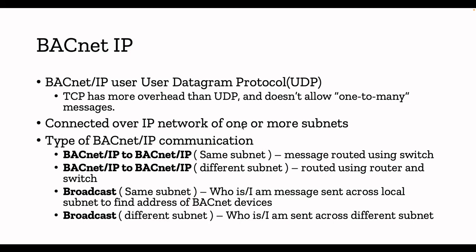BACnet/IP is connected over an IP network of one or more subnets. If you have BACnet devices that support IP, you can put all your devices in one subnet or create multiple subnets and deploy your BACnet devices. This helps segregate your devices into smaller categories and is a well-architected design. For example, if you have temperature sensors, humidity monitoring systems, and other control systems, you can create a separate subnet for each type of sensor.